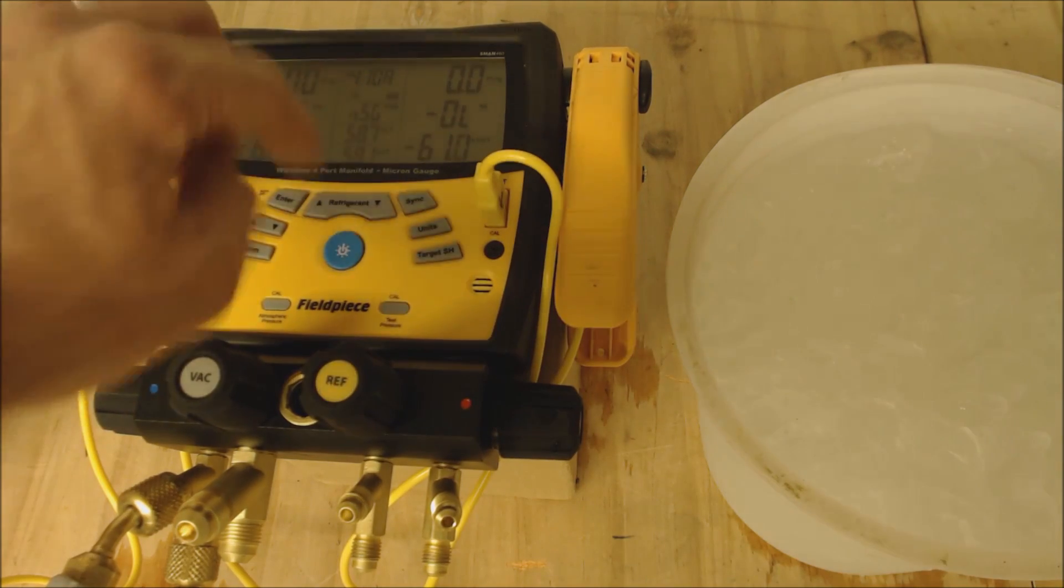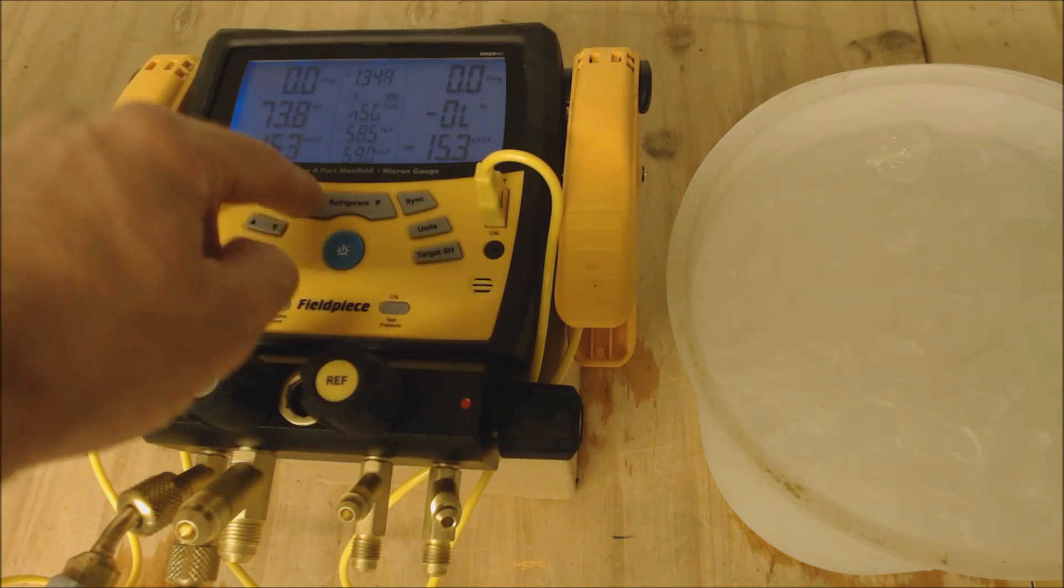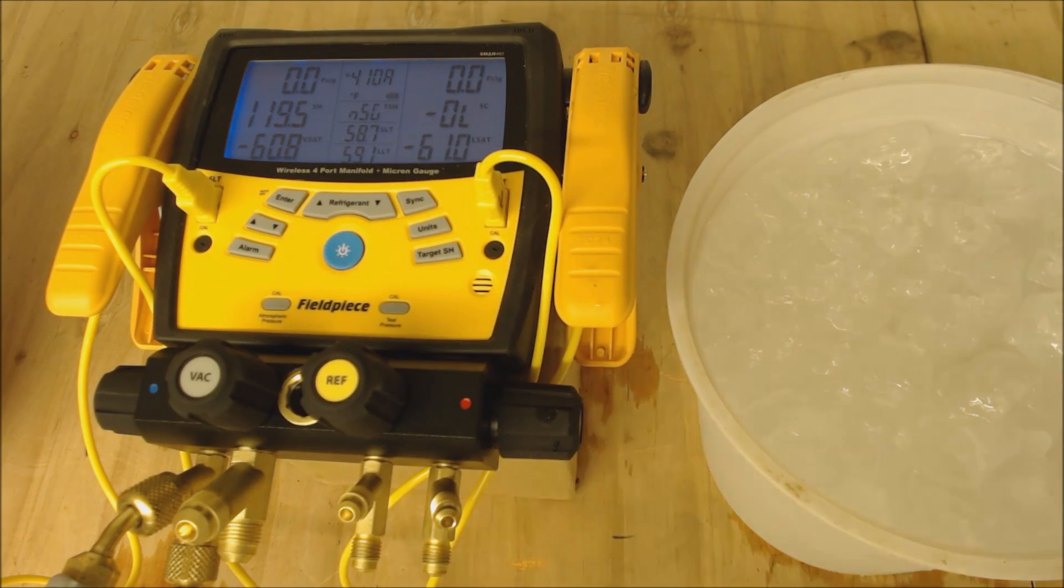We're going to turn it on. Right here it says R410A refrigerant. If you go up you can select whatever other refrigerants you want, like R22. We're just going to stick with R410A refrigerant. That's the one we left off with last, so it's the first one that will appear. You see your liquid line temperature here is reading 59.1 degrees.